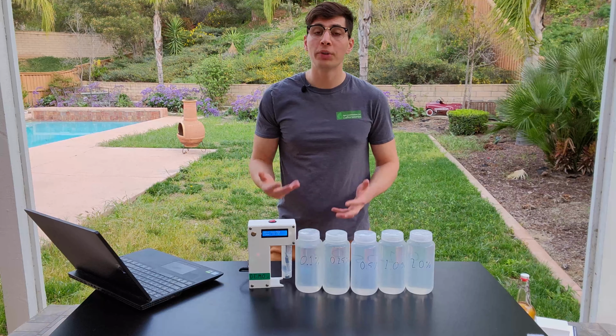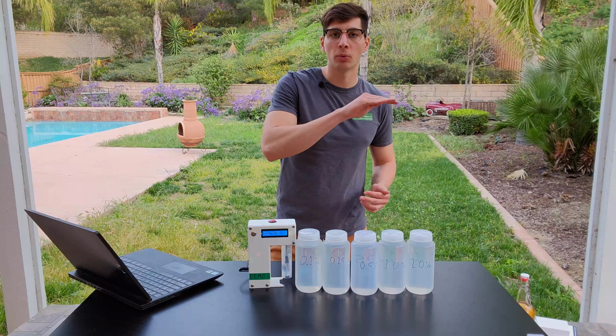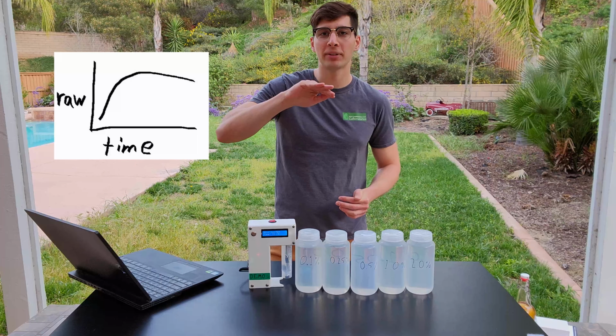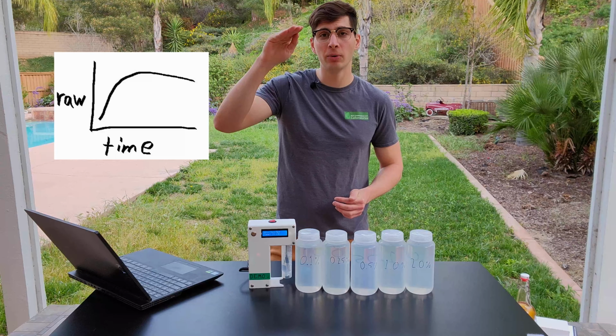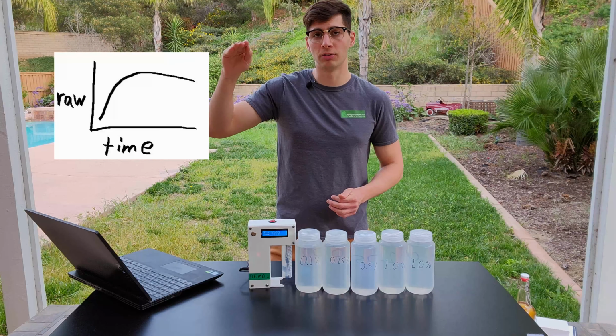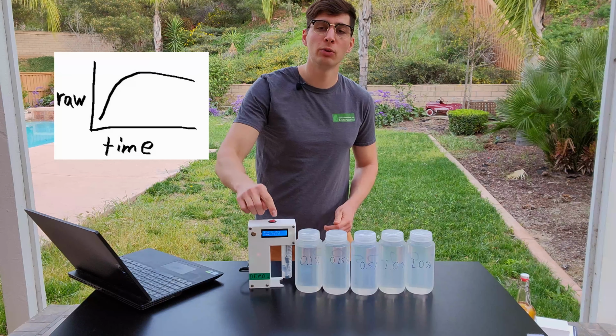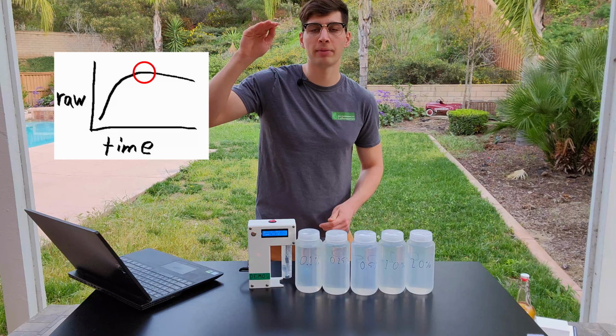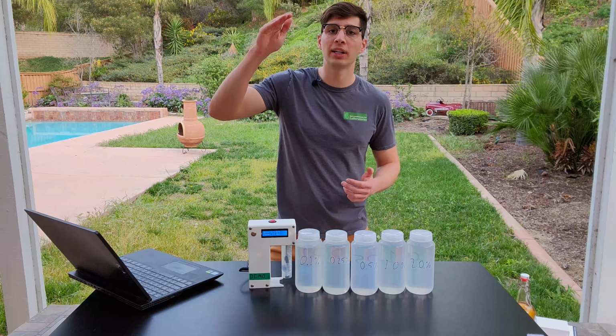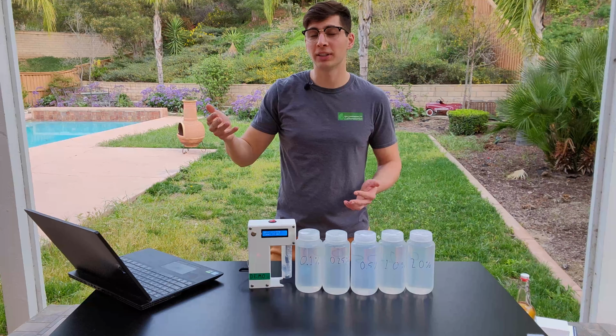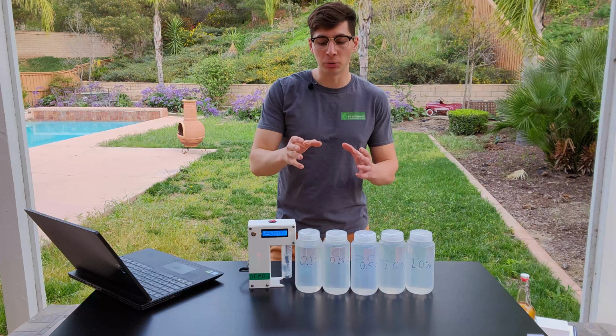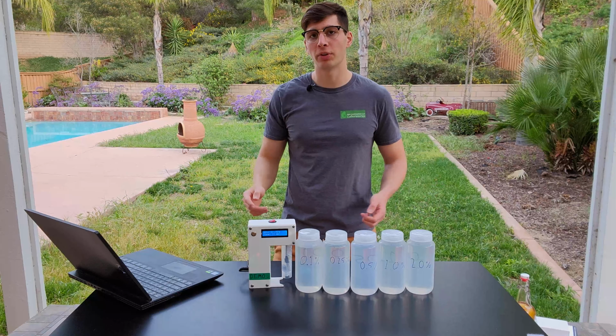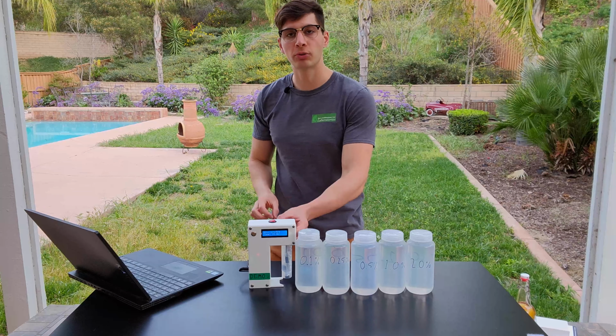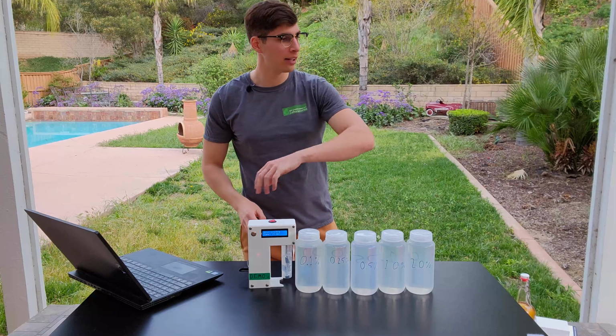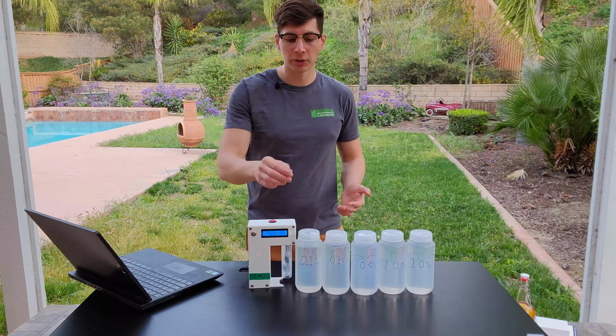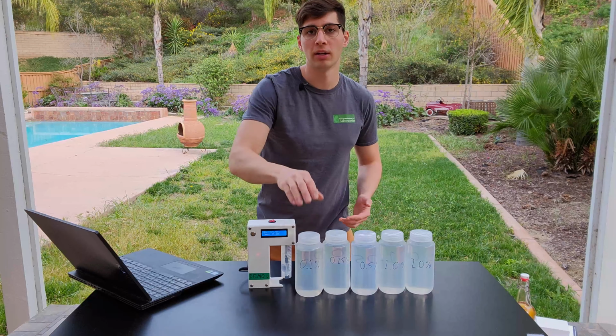So when you're measuring a sample, what will happen is the alcohol readings will rise very rapidly at first. They'll sort of reach a plateau, and then they'll very, very slowly start falling back down again. The reading on the right is useful because it sort of records where the top of that plateau will be. The fact that the readings fall a little bit towards the end is also significant because this means that you shouldn't ever measure any sample more than once. So once you pour it in a tube and you screw it into the device and you get the reading for that, you should throw that sample away. And if you want to measure it again, you can pour from the original bottle.